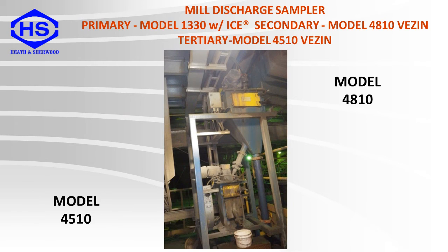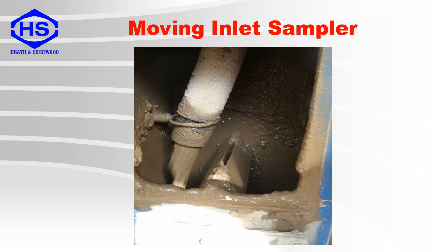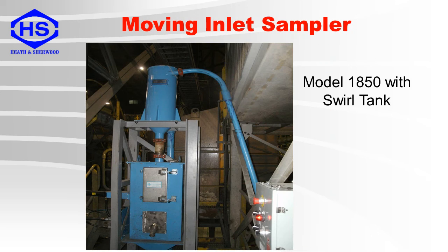Here is an example of a metallurgical sampling station. The primary is a linear cross-cut sampler, and the secondary is a rotary Vezin sampler. The final sample then goes into a bucket. One note about secondary samplers is that for each cut of the primary sampler, the secondary sampler should take a minimum of four cuts. This is an example of a moving inlet sampler, where you can see the hose at one side of the cutter. In this case, the sampler has a swirl tank located above the moving inlet sampler, which is used to dissipate any pressure in the sample line before going to the sample cutter.